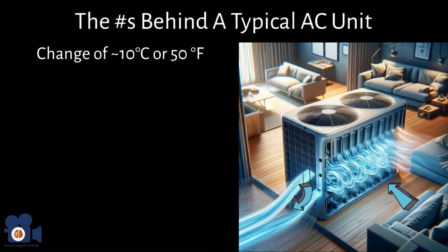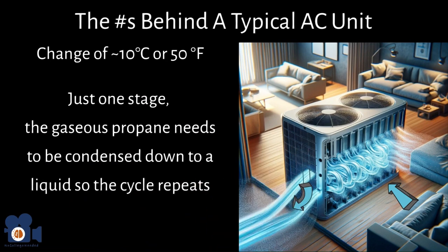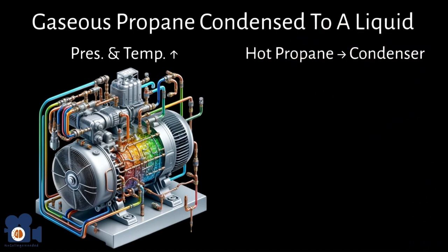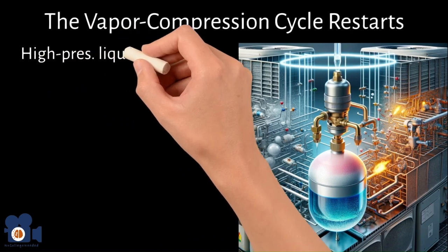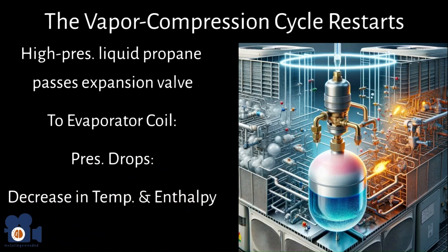Keep in mind this is just one stage. The gaseous propane needs to be condensed back to liquid so the cycle repeats. The vaporized propane is compressed by a compressor, increasing its pressure and temperature, which the AC unit needs to release. It sends the hot propane to a condenser where it transfers its heat to air pumped outside — which is why AC units discharge hot air and feel warm. The high-pressure liquid propane then passes through an expansion valve back to the evaporator coil, where pressure drops suddenly, decreasing temperature and enthalpy to restart the cooling process.